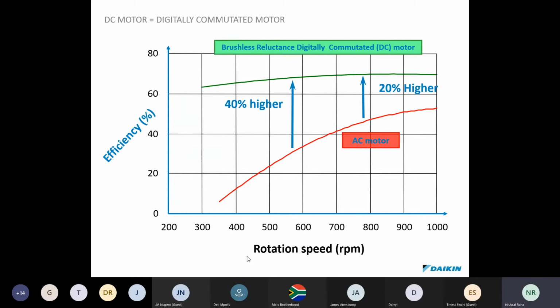Efficiency wise, the efficiency of the DC or digitally commutated motor is obviously much higher, right? It's 40% higher at rotational speeds of around 600 to 500 RPM. And as you go higher in RPM, like on a very hot day where the motor needs to do more work, you're looking at about 20% higher than what we currently have on full load.